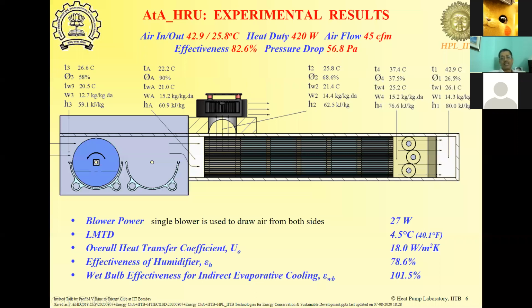Conventional air conditioning units, the coils would have pressure drop of anywhere between 150 to 200, 250 mm of pressure drop in the conventional heat exchanger. Okay. In this case, ambient air from the room, which is stale air, which is being exhausted at 26.6 degrees centigrade, and if it is around 60% RH, that is first humidified in the rotating contacting device in this case. And when humidified, the RH increases to 90% and the temperature drops to 22. So we have 22 degrees centigrade air available now to cool the 42.9 degrees centigrade air.